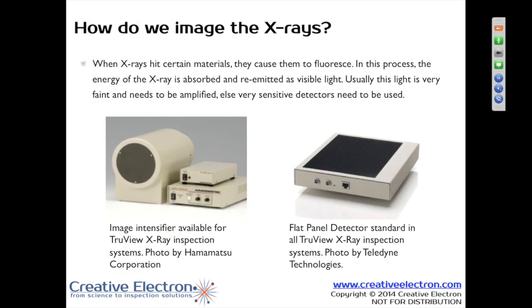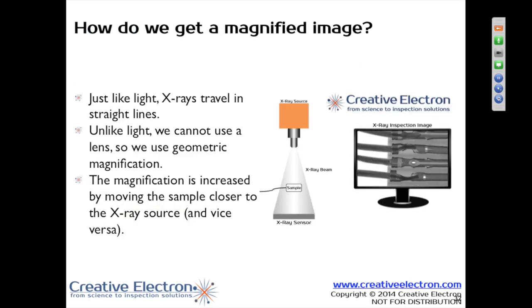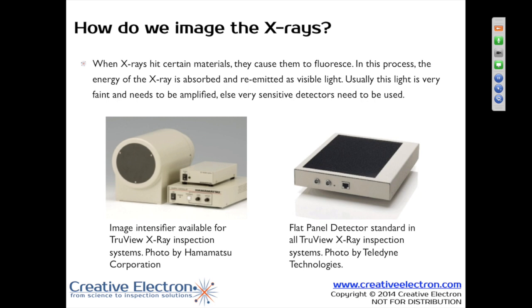X-ray detectors. In the good old days, we used phosphor-coated screens and you'd stand behind it and look at your image. Image intensifiers are essentially old school — they were developed in the 60s for medical applications. Essentially, it takes that very low energy image created with a scintillator and increases the light intensity or electron availability by about 36,000 times. It's the same concept night vision scopes use — they take available light, magnify it electronically, and convert it back to visible light. We're doing the same thing with an image intensifier.